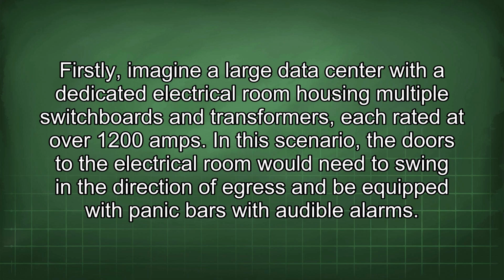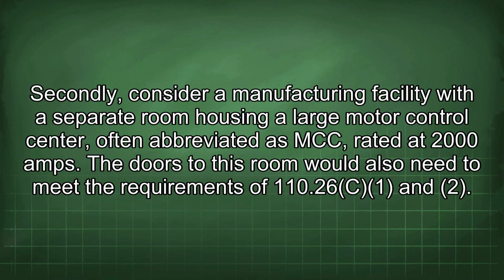Firstly, imagine a large data center with a dedicated electrical room housing multiple switchboards and transformers, each rated at over 1200 amps. In this scenario, the doors to the electrical room would need to swing in the direction of egress and be equipped with panic bars with audible alarms. Secondly, consider a manufacturing facility with a separate room housing a large motor control center, often abbreviated as MCC, rated at 2000 amps. The doors to this room would also need to meet the requirements of 110.26(C)(1) and (2).